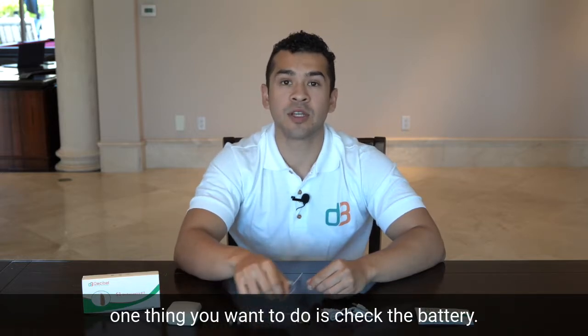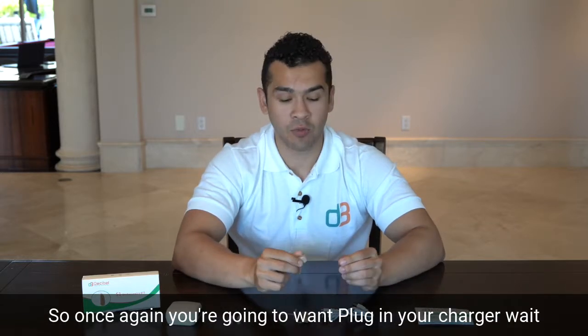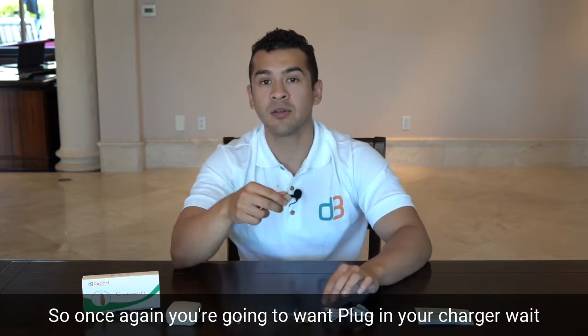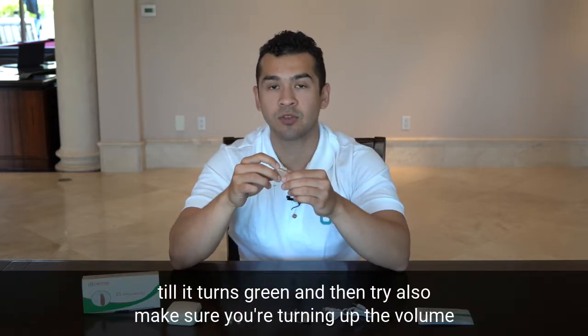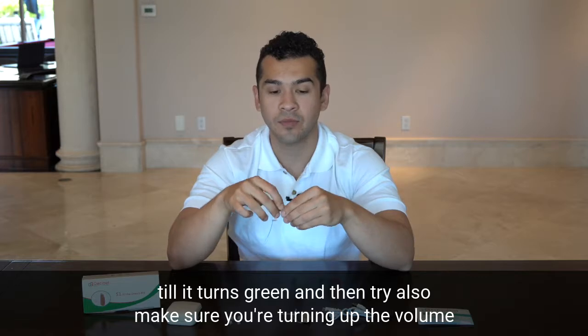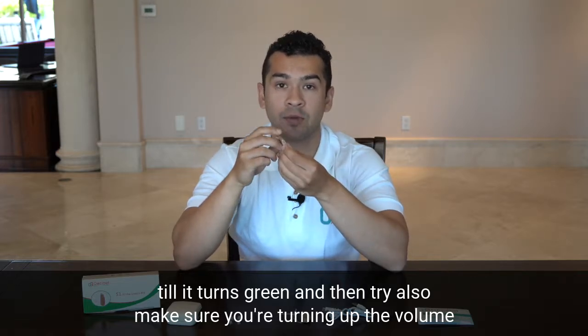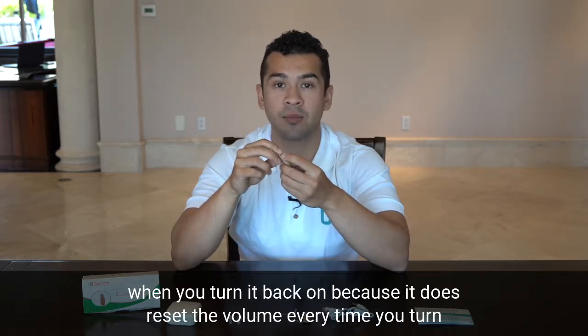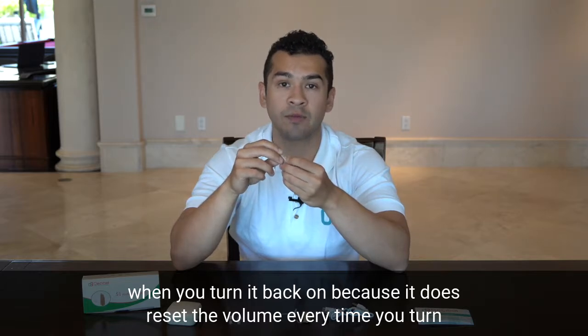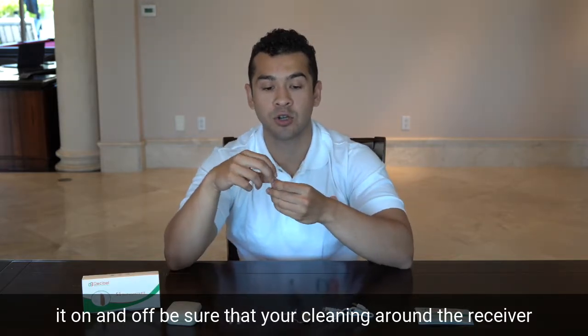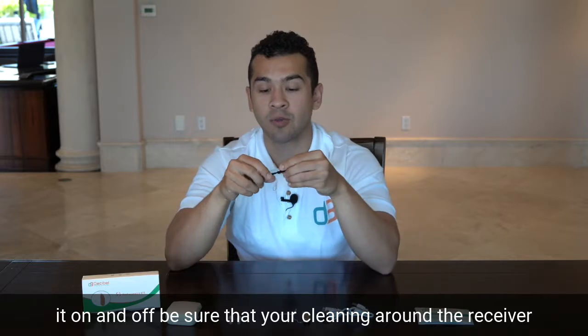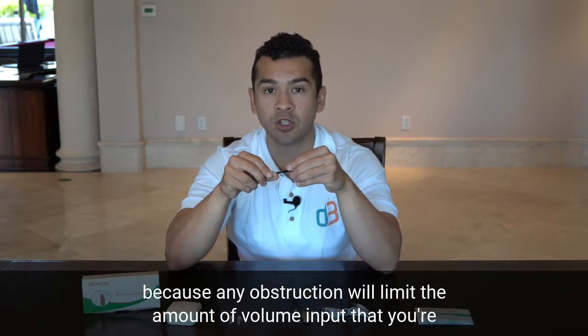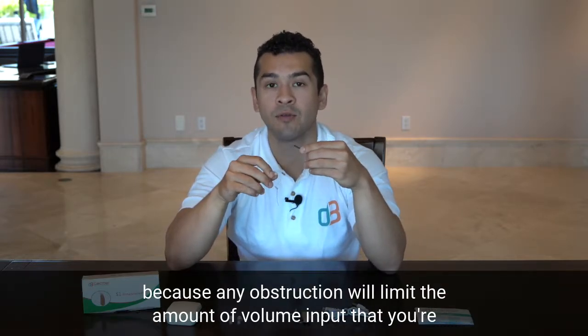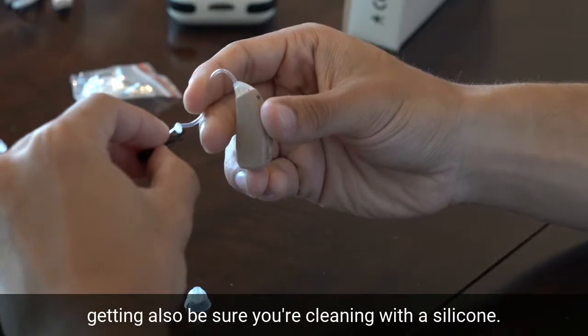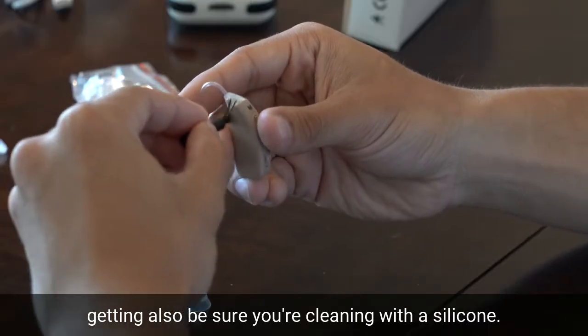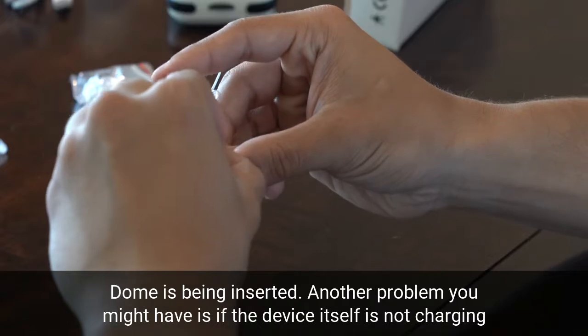The second problem you might run into is if the sound volume is way too low. One thing you want to do is check the battery. So once again, you're going to want to plug in your charger, wait till it turns green, and then try. Also, make sure you're turning up the volume when you turn it back on, because it does reset the volume every time you turn it on and off. Be sure that you're cleaning around the receiver, because any obstruction will limit the amount of volume input that you're getting. Also be sure you're cleaning where the silicone dome is being inserted.